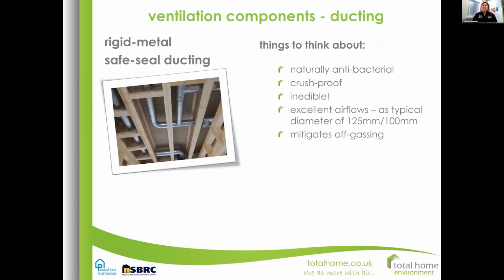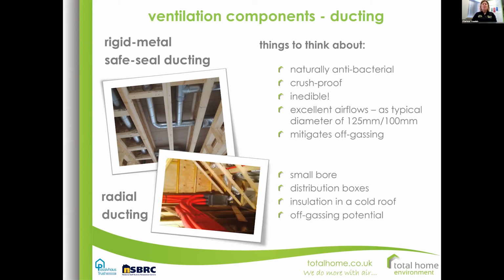So the next thing to think about is ducting. As a company, we would always specify rigid metal safe seal ducting. It's naturally antibacterial, nobody can crush it, no mice can eat through it, airflows on paper actually happen in practice, and especially when you're thinking about some of the units we've got the heat pump in, there's absolutely no off-gassing potential there. Another type is radial ducting.